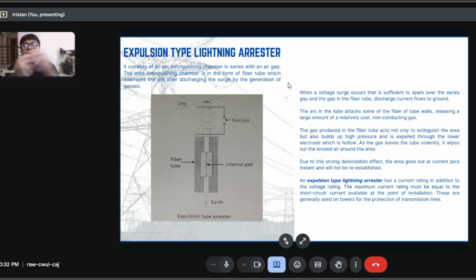So dito, it consists of an arc extinguishing chamber in series with an air gap. The arc extinguishing chamber is in the form of a fiber tube which interrupts the arc after discharging the surge by the generation of gases. When a voltage surge occurs that is sufficient to spark over the series gap and the gap in the fiber tube, it discharges and the current flows to ground. The arc in the tube attacks some of the fiber of the tube walls, releasing a large amount of relatively cool and non-conducting gas. So the gas produced in the fiber tube acts not only to extinguish the arc, but also builds up high pressure and is expelled through the lower electrode, which is hollow. As the gas leaves the tube violently, it wipes out the ionized air around the arc. Due to this strong deionization effect, the arc goes out at current zero instant and will not be re-established.